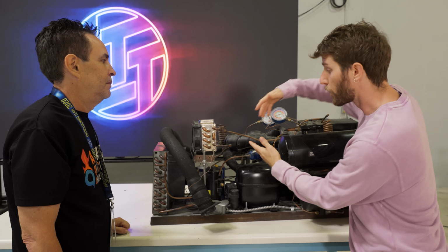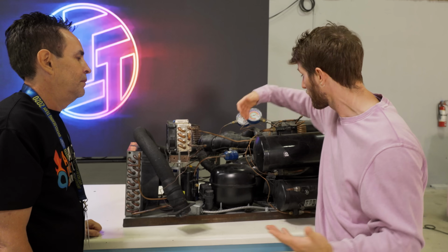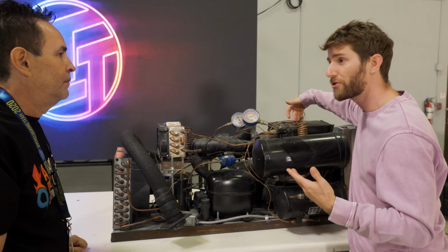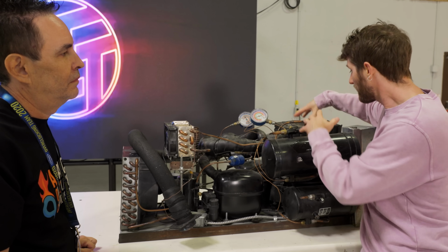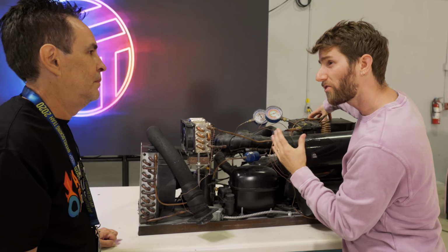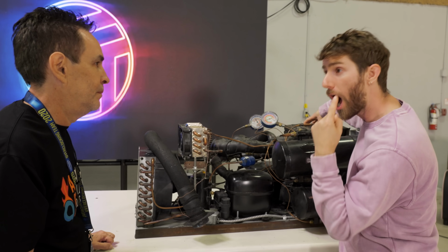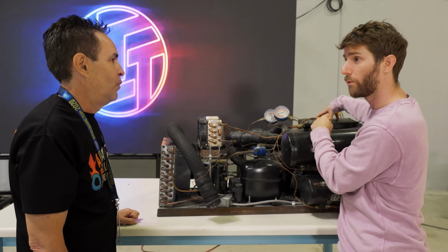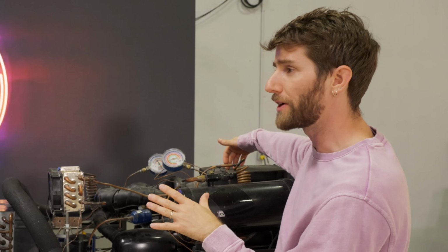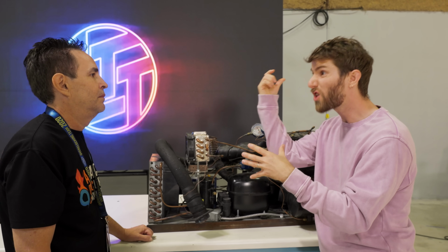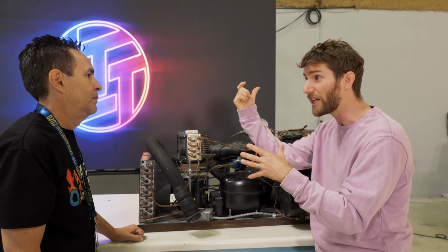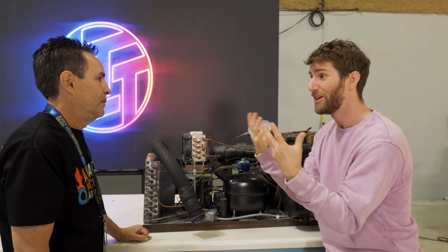But we're not doing that. No, because this is multi-stage, we're taking our cold side, our evaporator side, and going to a heat exchanger. So that means this inside here is the cold side of stage 1 and the hot side of stage 2. So that refrigerant, which for stage 2 starts at negative 40 C on the hot side, where does that go?